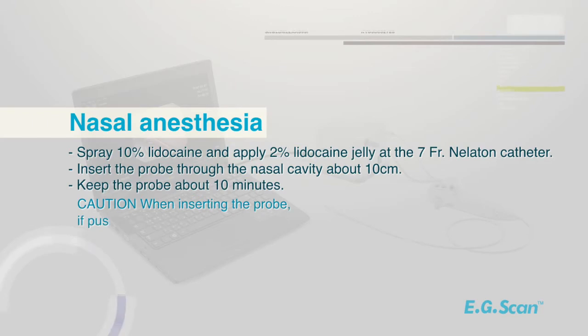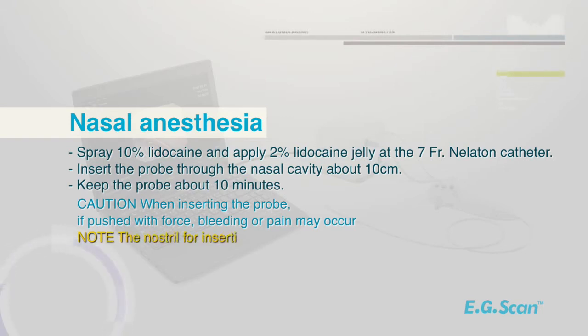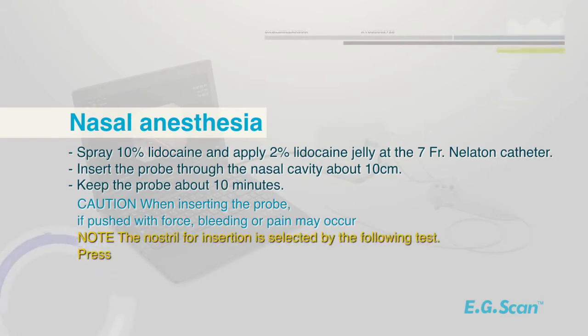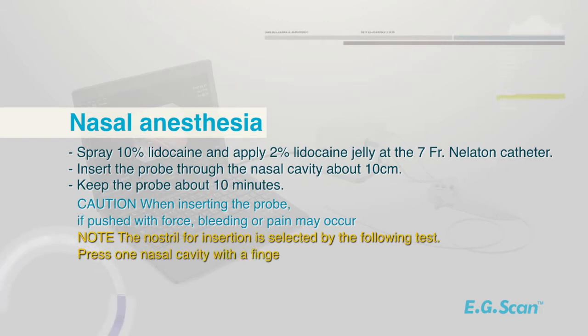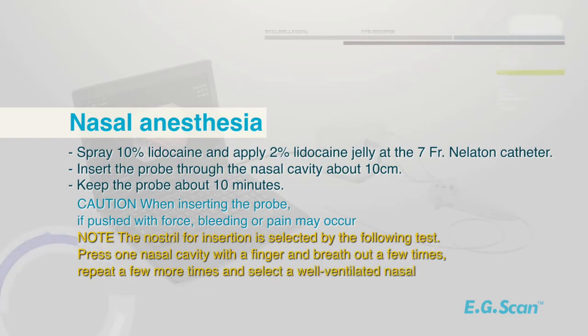CAUTION: When inserting the probe, if pushed with force, bleeding or pain may occur. Note: the nostril for insertion is selected by the following test — press one nasal cavity with a finger and breathe out a few times. Repeat a few more times and select the well-ventilated nostril.